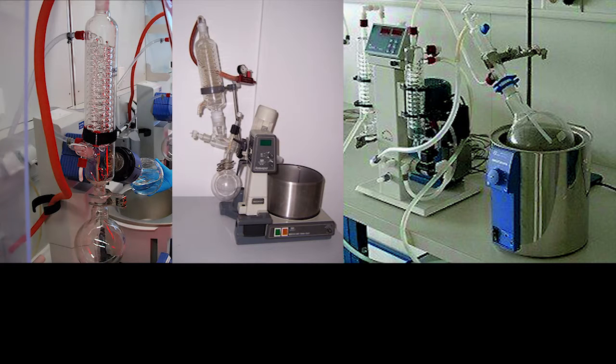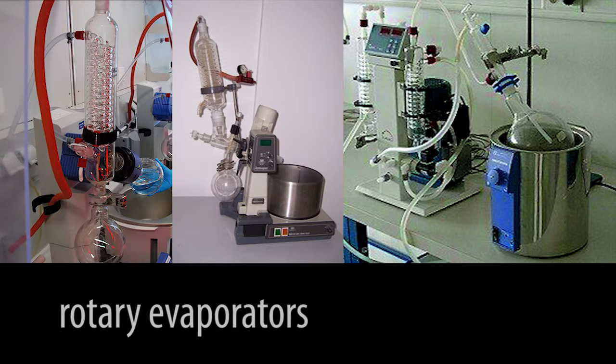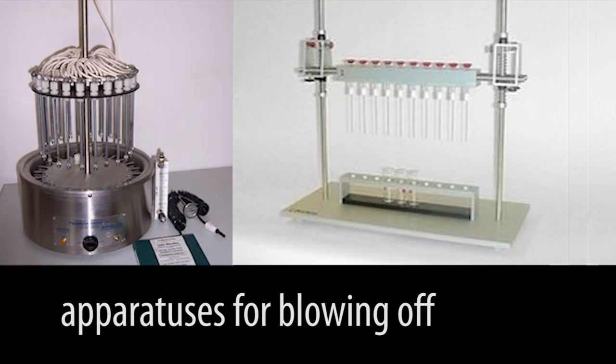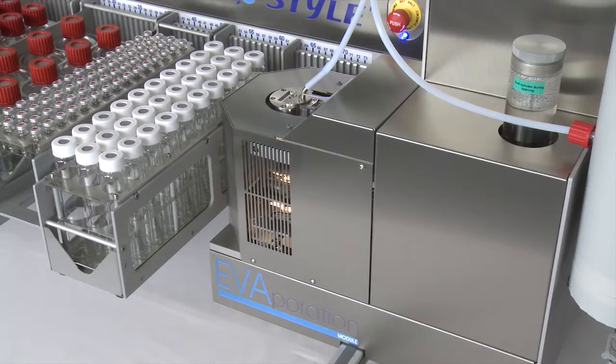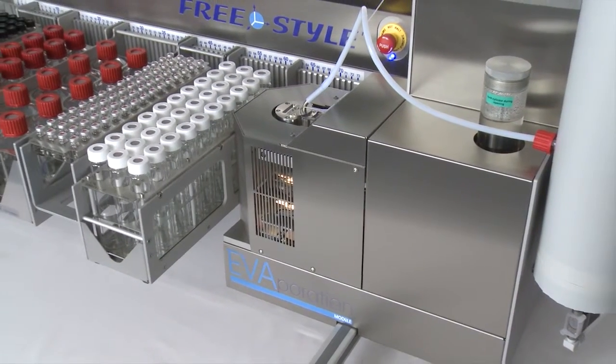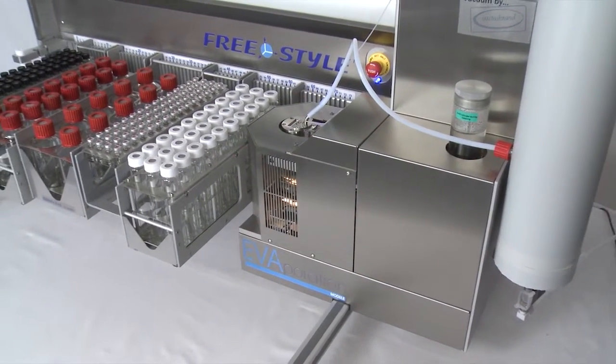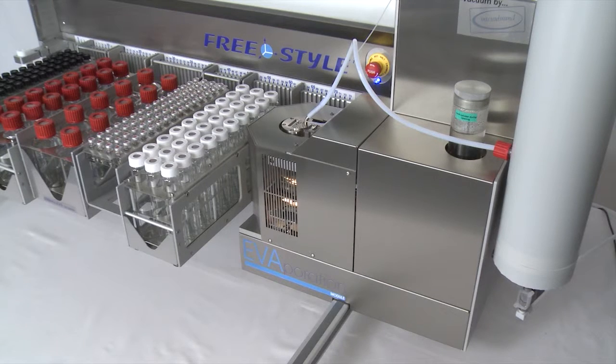The traditional ways of evaporation include rotary evaporators and apparatuses for blowing off with nitrogen. The new freestyle system integrates both options and is far more environmentally friendly by means of controlled solvent recovery.